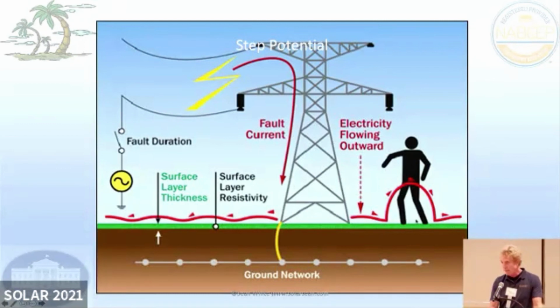There's something called step voltage. I just think it's kind of interesting. If a high voltage line or something falls, and you took a big enough step, there might be different voltage in different places. And if there's a different voltage in a different place, the current might go through your body, and that kind of hurts. So just be careful of that. If lightning comes, stand on one foot. That's all we're trying to say. And be careful of putting ground rods that are not bonded to each other before they connect to you. You don't connect ground rods together through an electrical system. Ideally, according to different theories, there are different ways of doing that.